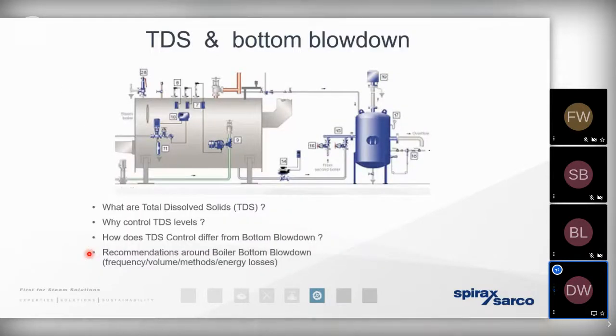Other ways that we can optimize in an existing steam using system is by looking at the blowdown. Now, we've spoken previously about what the blowdown controls are, what they do. And that really comes down to the understanding that the chemicals and minerals that are present in the water, together with the chemicals and minerals that we add to the raw water, are going to behave in two different ways. And the analogy that I usually use is it's like having a cup of tea at home. You put a spoon of sugar in your tea, it dissolves. You put a spoon of sand in your tea, and it falls to the bottom of the cup.